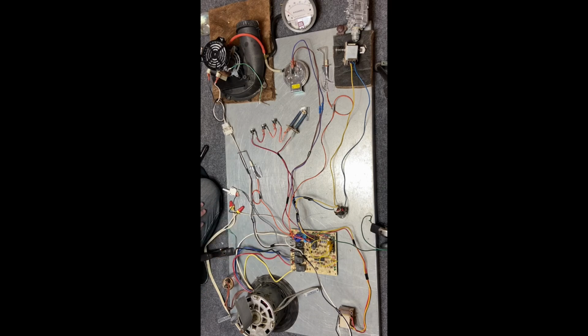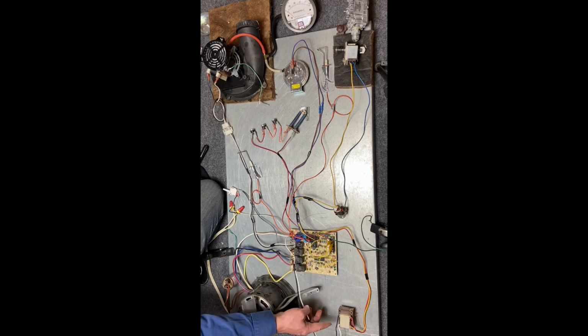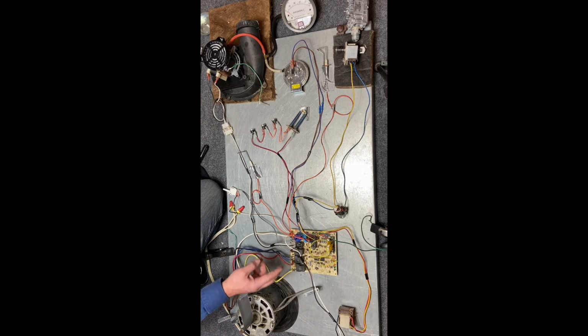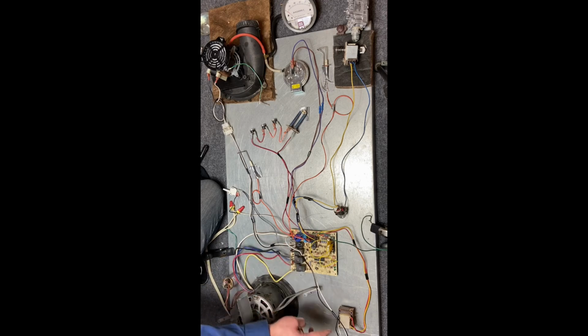Now from there we can look at everything on here, but I specifically want to focus on the XFMR, just like we did when we talked about the control board. XFMR, short for transformer, and we have a neutral wire. So it's 2 wires going to power our transformer. So if I want to make sure my transformer is working, I can check here to see, am I getting 120 volts to my transformer?